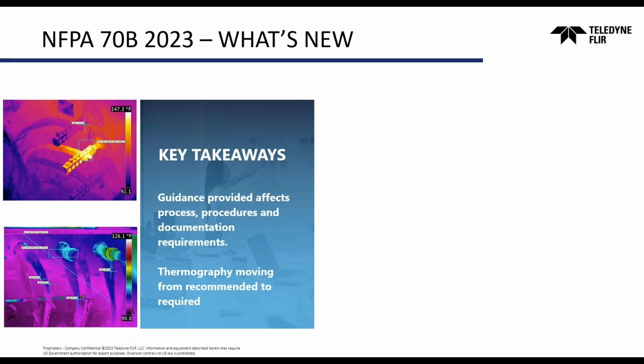That's a big shift within the guidance, where in the past it was something they recommended that you do. Now they very explicitly call it out as a required activity and task. In the guidance itself, if you look at the documentation of recommended maintenance activities, regardless of the asset type being maintained, the very first line on that list of activities is a thermal inspection. We're going to get into the specifics on these a little bit more.